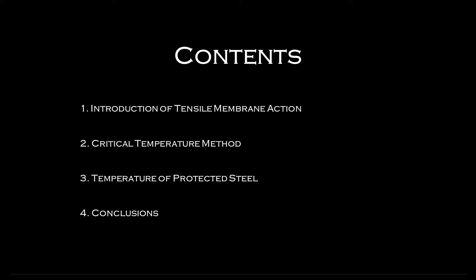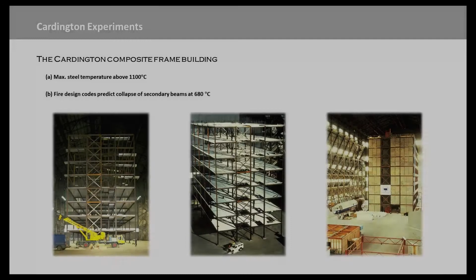Fire resistance is determined by the ability of the construction to achieve adequate insulation, integrity, and load-bearing performance. These three requirements are to prevent the three modes of fire spread from one compartment to another compartment. The insulation requirement is concerned with prevention of excessive temperature on the unexposed surface of the construction to cause further ignition. This is quantified by limiting the temperature increase on the unexposed surface to be no more than 140 Celsius on average and 180 Celsius at the maximum. Integrity failure occurs when fire burns through the construction. Load-bearing capacity is necessary to ensure that the structure does not fail, leading to fire spread from one compartment to another.